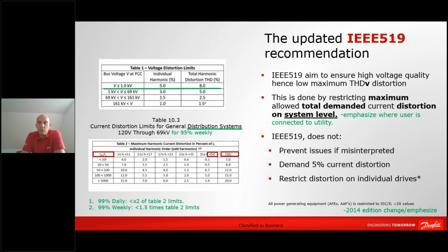And that means if you have 1,000 drives and 1,000 direct online motors in your installation, then the IEEE 519 standard applies for the 2,000 pieces of loading you have on your installation, and not for the individual 1,000 drives in isolation. And that's extremely important to understand, because if you start now mitigating each and every harmonic on your individual loading, then you will end up spending a lot of money on something that doesn't give you any value.